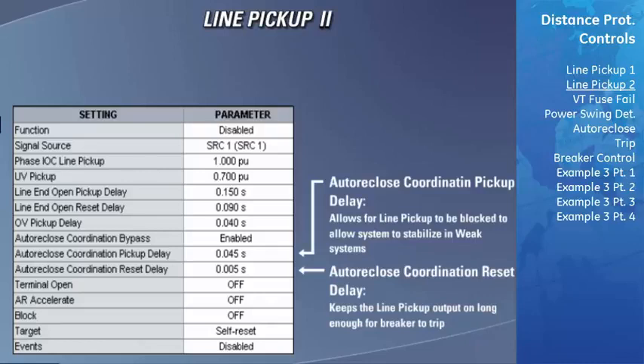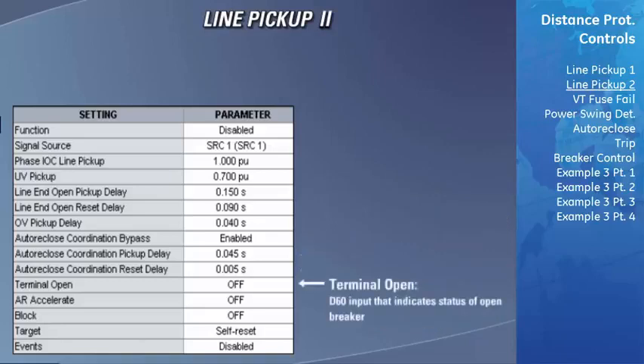This field sets the length of time to block the line pickup element after reclosing to allow for the unfaulted system to stabilize. The auto-reclose coordination reset delay setting will specify how long the line pickup element will hold the trip output flag in the on state to ensure the breaker has enough time to complete the tripping sequence. This setting should be set to at least the breaker tripping time. The terminal open field is used to indicate to the line pickup element when the breaker is open. In this field, you will need to program which D60 input is indicating the status of the open breaker. Normally, this would be a contact input that is wired to the 52B contact of the breaker.